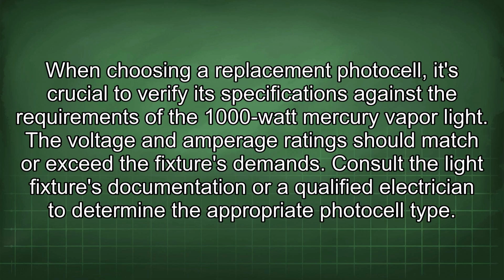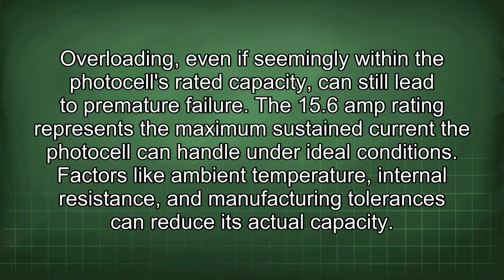When choosing a replacement photocell, it's crucial to verify its specifications against the requirements of the 1000-watt mercury vapor light. The voltage and amperage ratings should match or exceed the fixture's demands. Consult the light fixture's documentation or a qualified electrician to determine the appropriate photocell type. Overloading, even if seemingly within the photocell's rated capacity, can still lead to premature failure. A 15.6 amp rating represents the maximum sustained current the photocell can handle under ideal conditions. Factors like ambient temperature, internal resistance, and manufacturing tolerances can reduce its actual capacity.